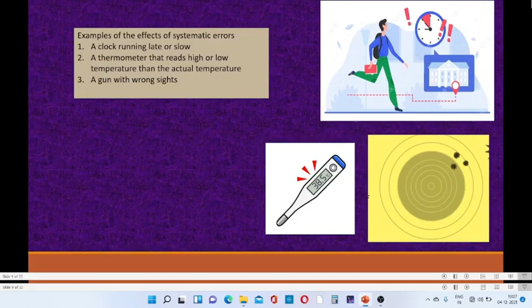Now, how to deal with these systematic errors? Systematic errors cannot be corrected by statistical methods. As you have seen, that person measured his weight many times, maybe 15 or 20 times, and every time he was 10 kgs overweight. So repeating your measurements 15 times, 20 times, 500 times, 1000 times is not the solution to fix systematic errors. They are inherent errors that are associated with the instrument. They have to be treated with different mathematical tools. And the first thing we can do is to use calibrated instruments.